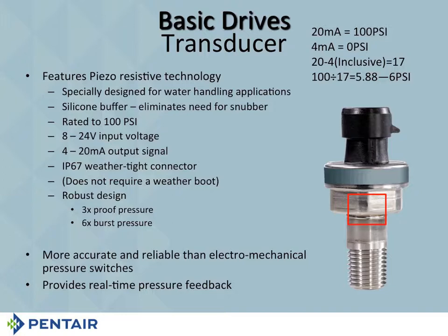And this is why, if you want to change that transducer and put a heavier duty transducer in there, you can do it, but make sure that you go in and change your sensor value too, because the bottom line is a 300-pound transducer is actually recording 18 psi per milliamp. So that would really throw off your pressure readings and cause you lots of anxiety. So 4 milliamps equals 0, 20 milliamps equals 100. That's 6 psi, 5.88, 6 psi.